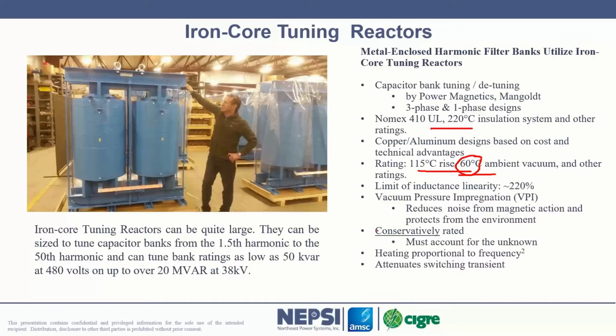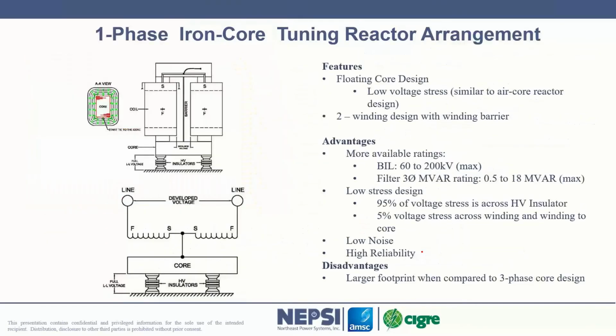And be conservative with your harmonic current ratings again, because if you pick wrong and the reactors are saturating because you picked wrong, or an air core reactor is overheating because you didn't put enough current rating in the reactor, you will have a filter system that can't operate.